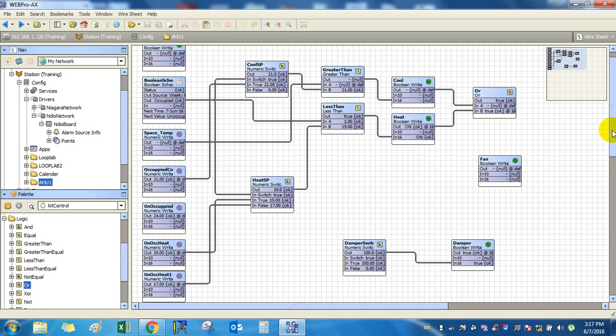Okay, so here you will see now your temperature is less than your occupied heating set point, which is 19. Here your space temperature is less than your heating set point, so your space is calling for heat, your heating is on, your fan is running and damper is open. So once the temperature is met, let's say it goes to 19, as soon as your temperature is 19, your space doesn't call for heating now and your heating is off.